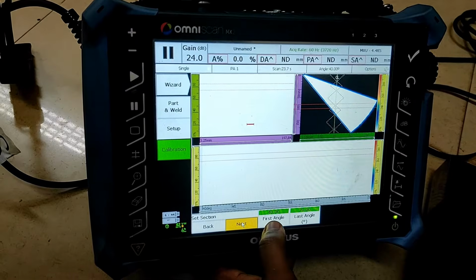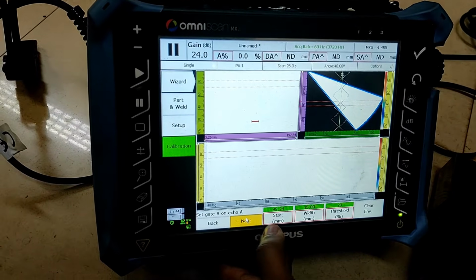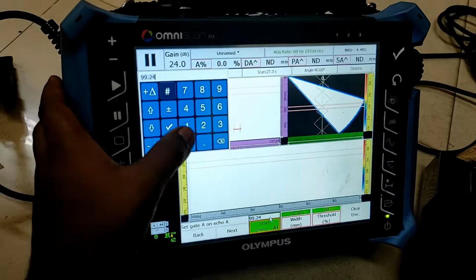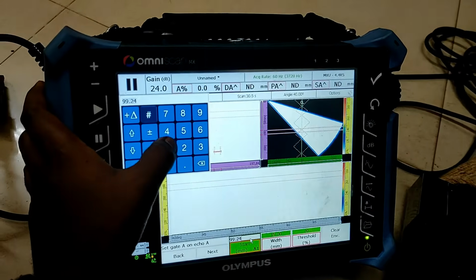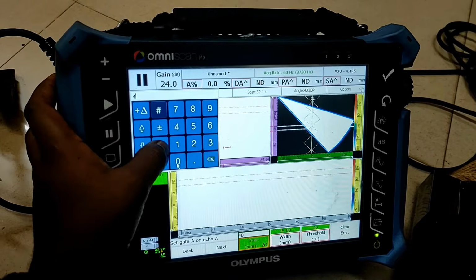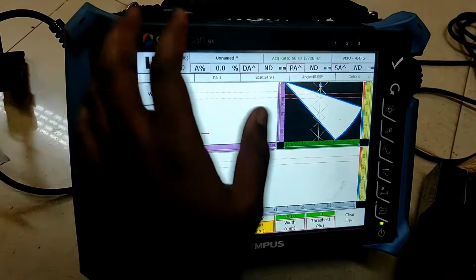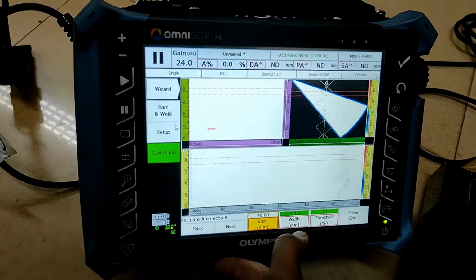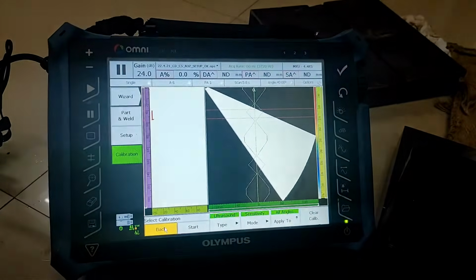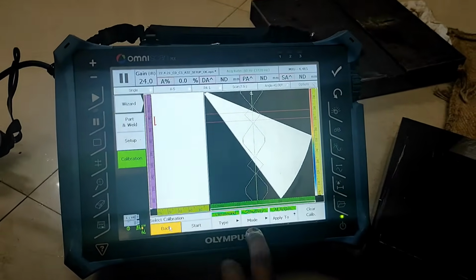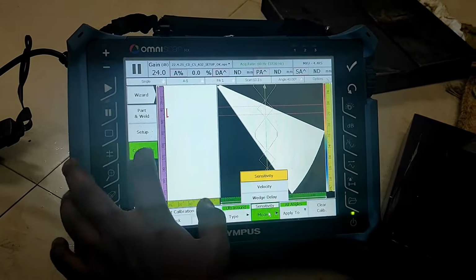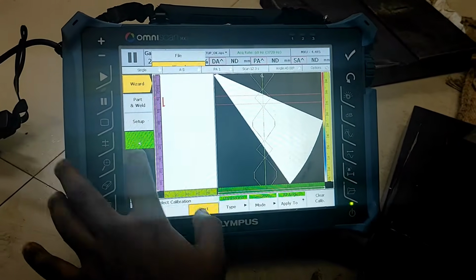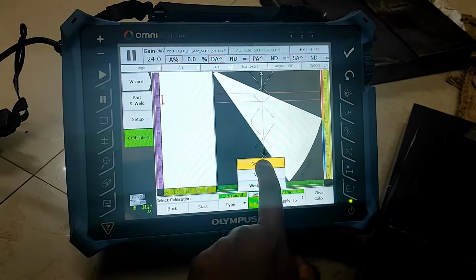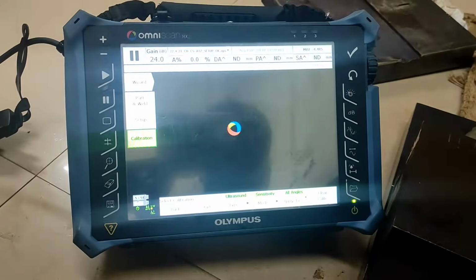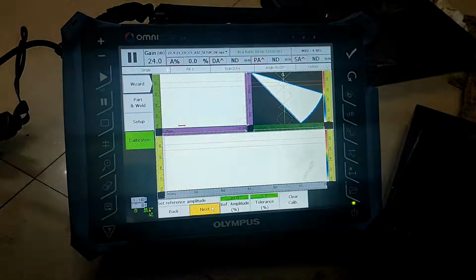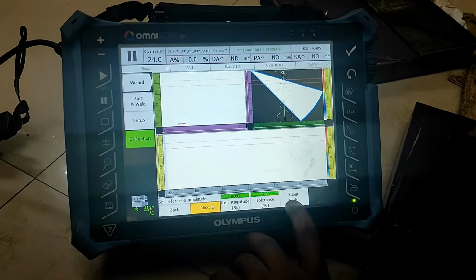Now next 40 to 70 angle. Next now we are going to give the start. This is very important. The start should be now at least 40 because we are going to catch the 45 mm hole. Now we are going to do the sensitivity calibration. For that we have to go to the sensitivity in the wizard calibration, and go to the mode sensitivity. Just start it. Now the amplitude is 80% and tolerance 5%.